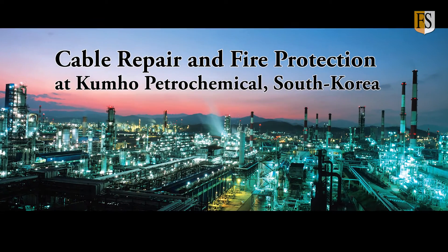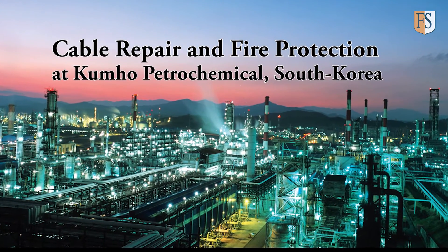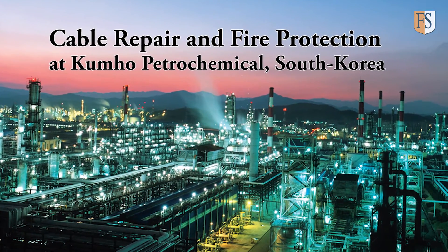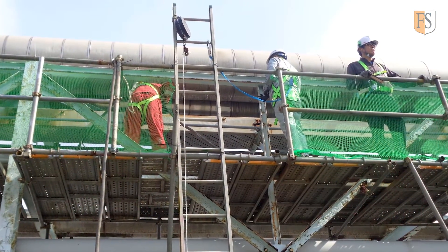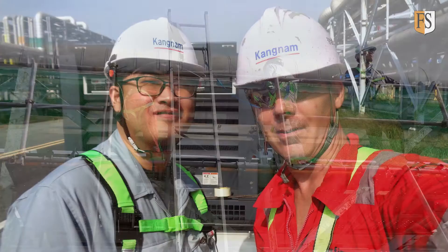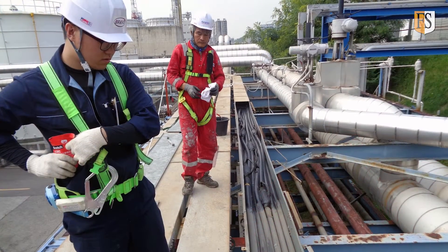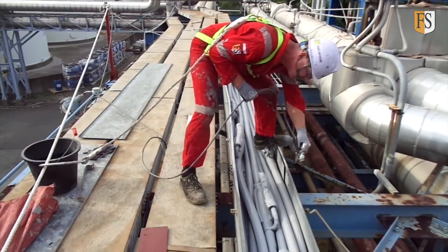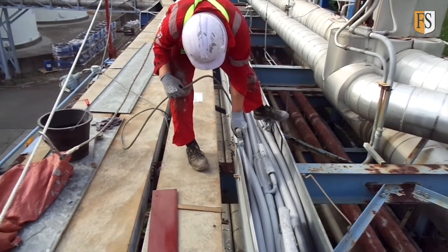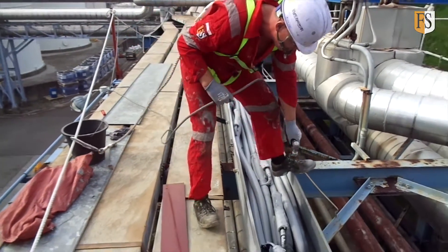In October 2016, Fire Security was chosen to do a pilot project at the Kumho petrochemical plant in Yosu, South Korea. In a joint operation with our agent Kangnam Drive, our objective was to protect areas where the spliced cables were located. Kumho had already experienced a fire which started in a splice and spread through the cable routing, probably caused by water that ingressed the cable splice.